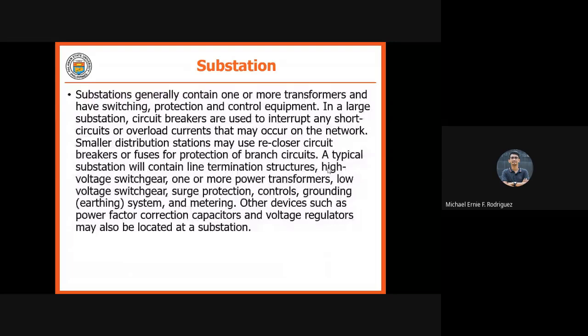And then sa substation, meron tayong one or more transformers na merong mga switching, protection, and control equipment. Mamaya isa-isay natin yung mga equipment or mga components na isang substation. In a large substation, we have circuit breakers na ginagamit para ma-interrupt yung mga short circuit tsaka mga overload. Pag mga maliliit na distribution substation, meron tayong mga recloser, circuit breakers, or fuses na ginagamit as protection. So, ang isang typical na substation, we have line termination structures, high voltage switch gear, one or more power transformers. We also have a low voltage switch gear. We have surge protection, important ito.